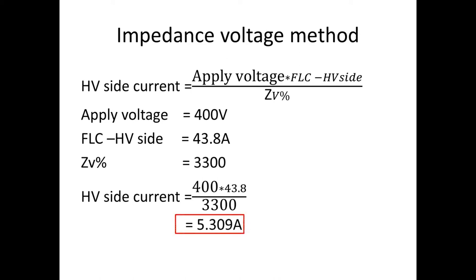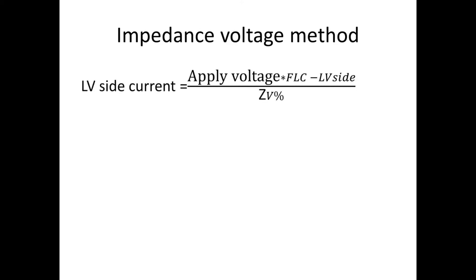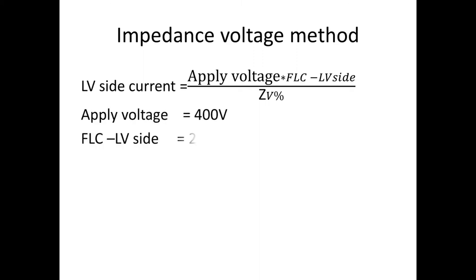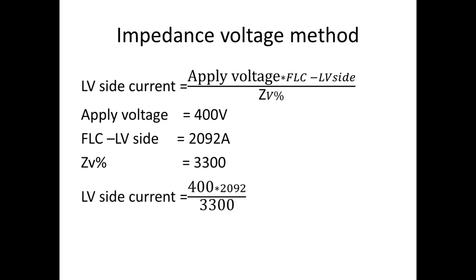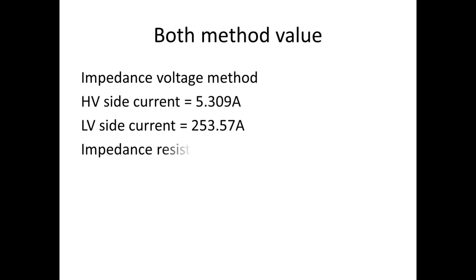Now for the LV side current using the same formula: the full load current of the LV side is 2092 A, giving 253.57 A. So we have two methods, and both give the same values. The results from both methods are consistent.